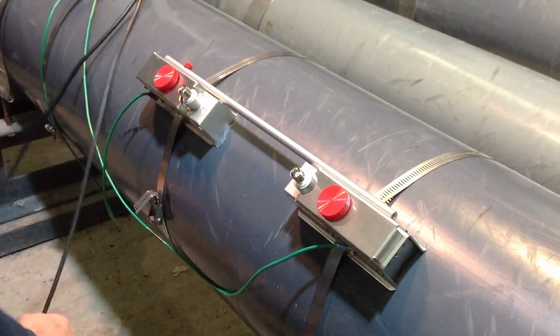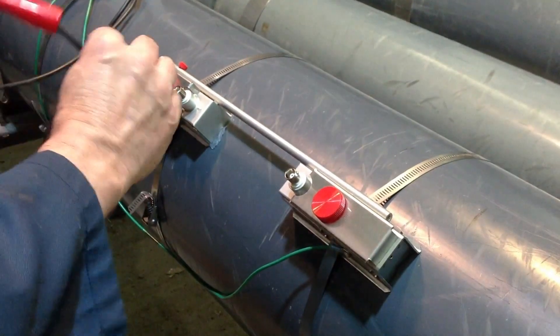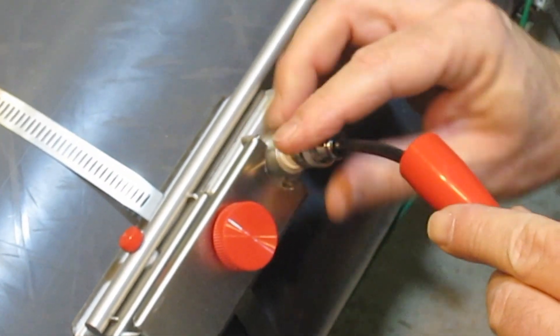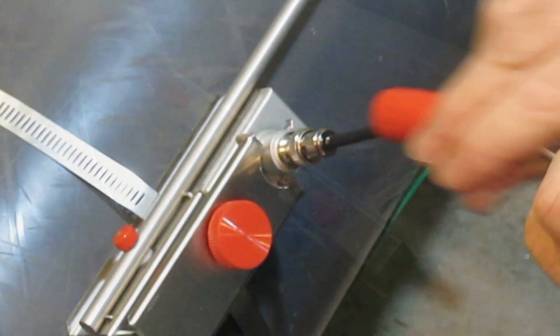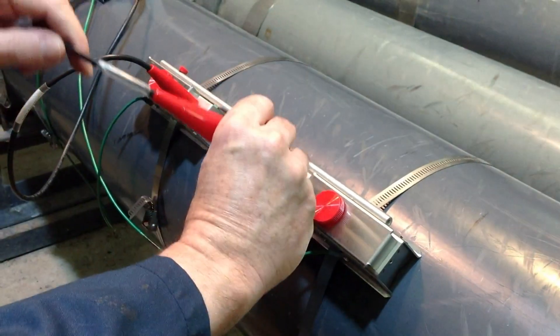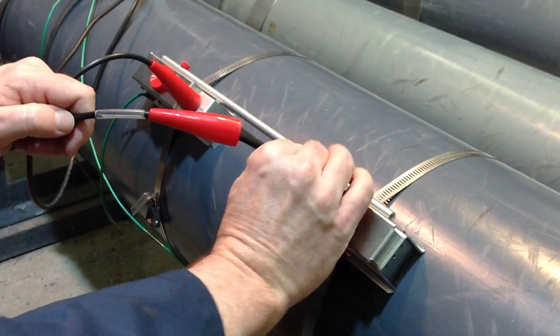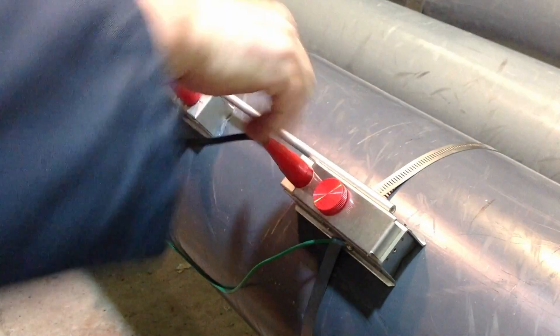Now we connect the transducers to the TTFM 1.0 flow meter electronics. The coaxial cables use BNC connectors and couple to the transducer. The BNC connections are protected by seal jackets, which can be filled with coupling compound in wet applications.